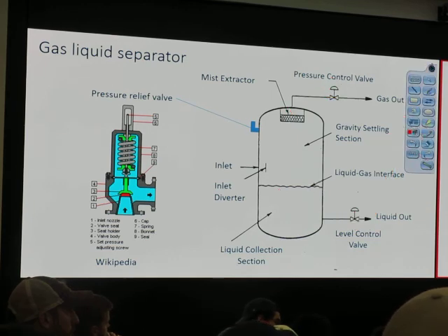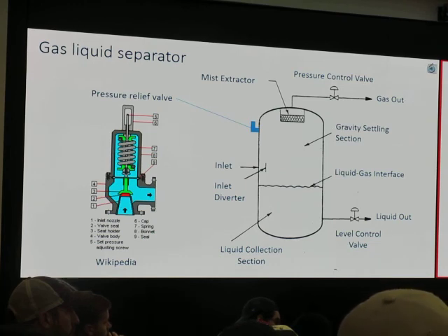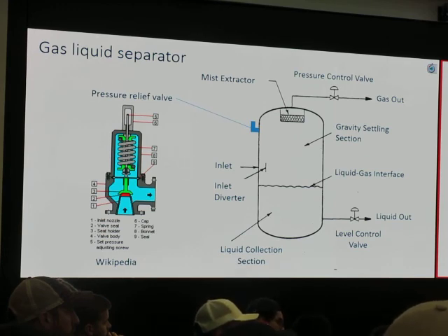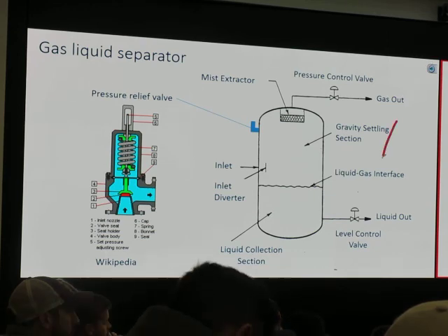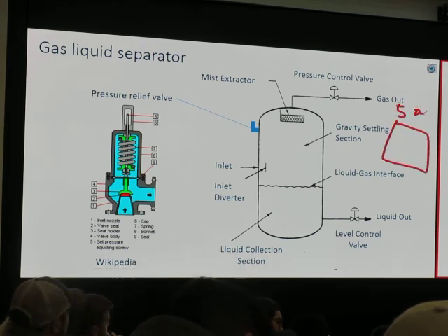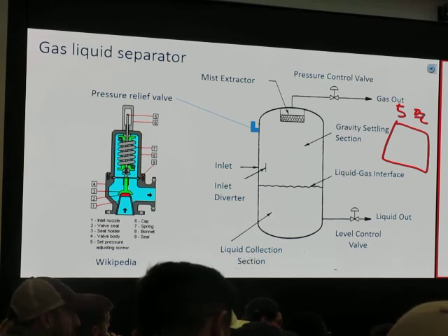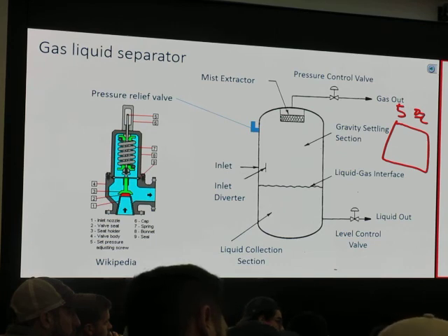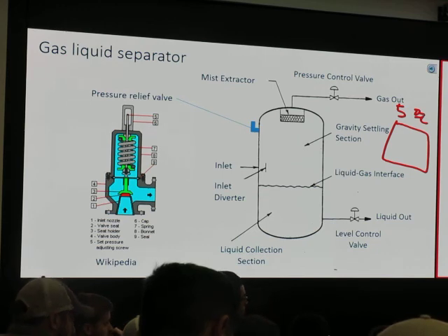At your house, you probably have a garden hose on a water system, and it's 40 psi behind it. When you open the valve, what do you have at the end of the hose? Atmospheric, right? So that valve has taken the pressure drop. That's the same thing that's happening with the liquid level valve. We can hold a higher pressure because the separator can dump into a free water knockout. The free water knockout can be rated higher, but when those vessels dump into the tank, it's all right. You're taking the pressure drop across the valve, dissipating the energy there, and then it goes to your tank.